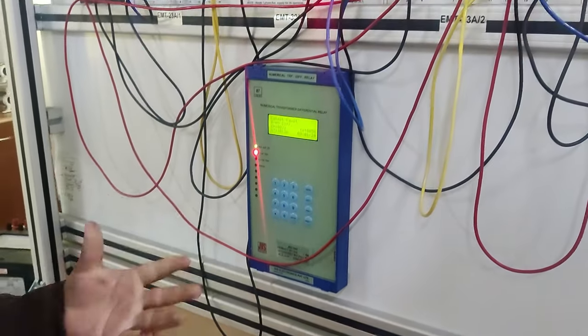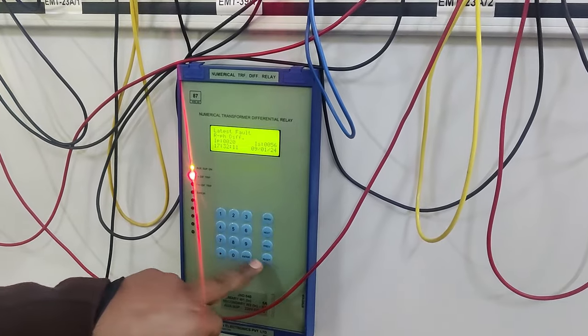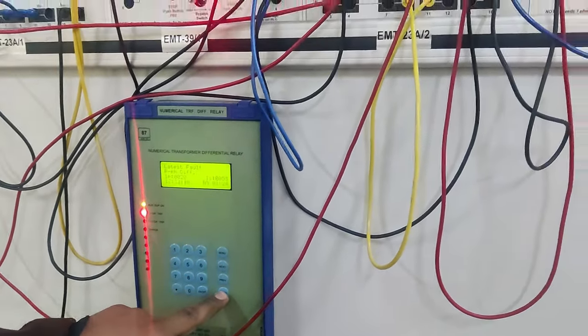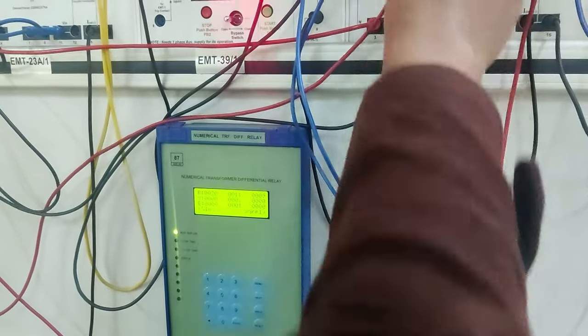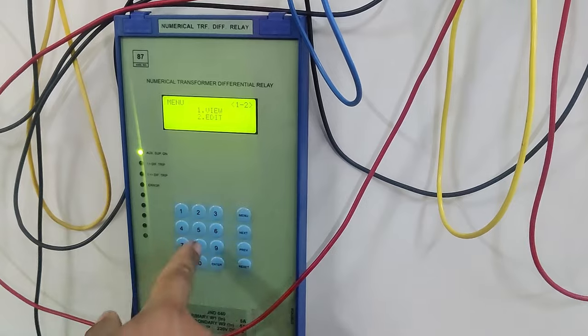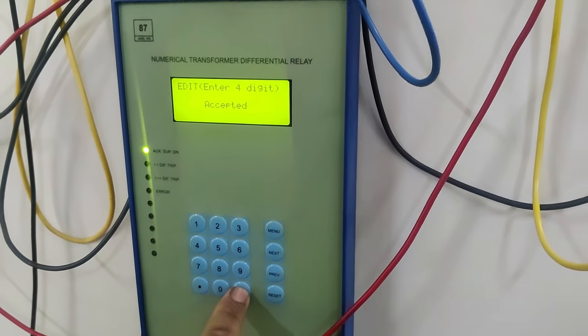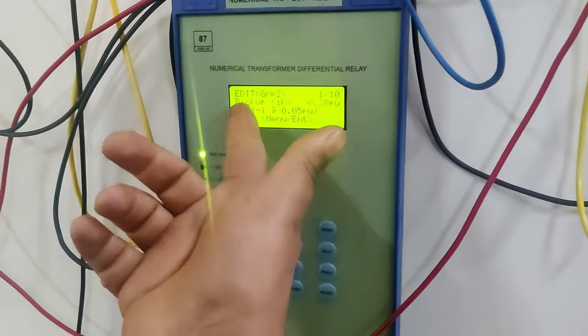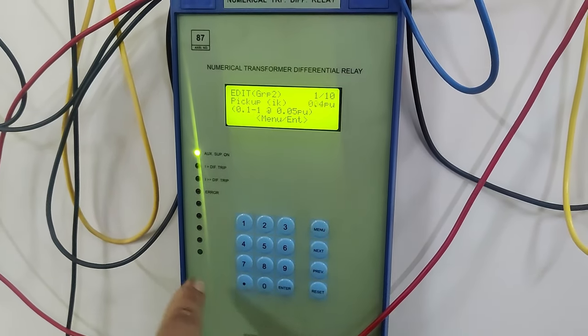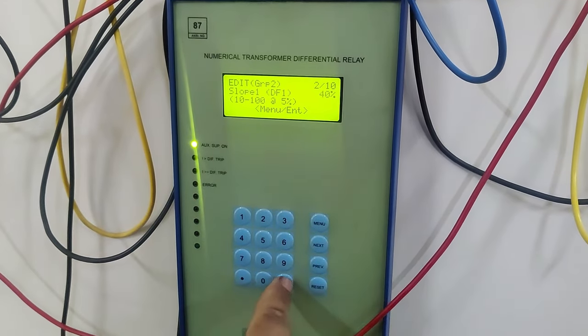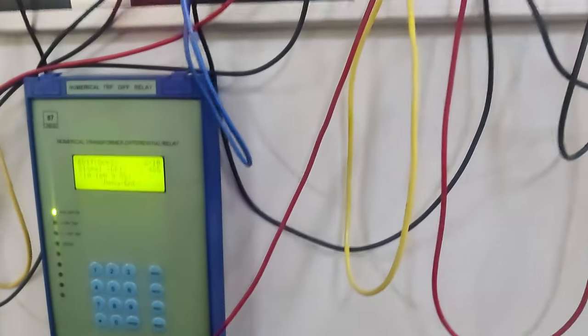This was all about how we can plot the basic characteristics of this differential relay. For resetting, we can use the reset option — we can go to the reset option and the fault has been cleared. Now I can show you once again — we can go to menu, go to edit options, it will demand for the password, and after giving the password you can similarly change the characteristics. You can see the pickup was initially 0.2 per unit — you can change it to 0.4 per unit. Accordingly you can change the slope to 40 percent, and then taking the readings and plotting the graph. Thank you so much.